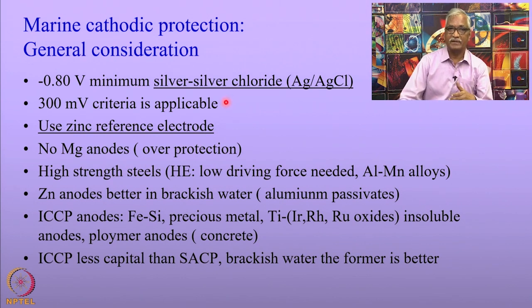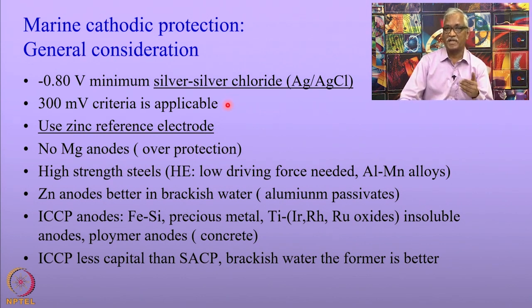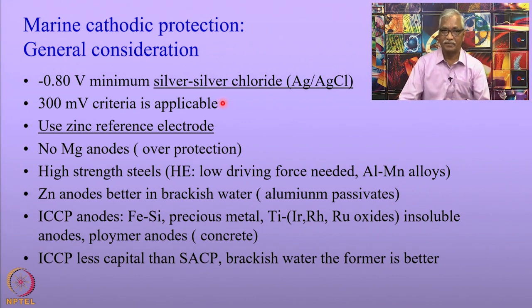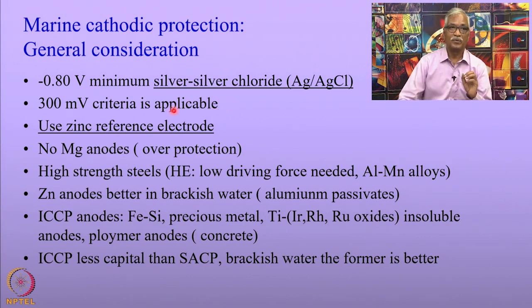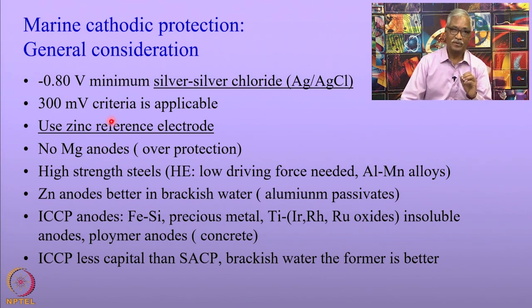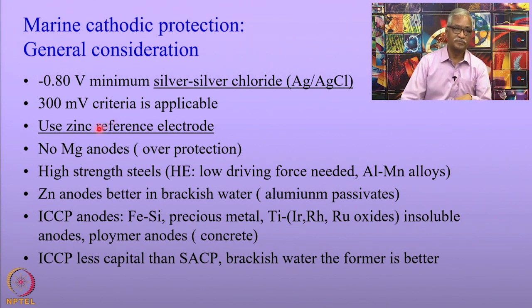Because the marine environment is high in chlorides, the copper-copper sulfate electrode is seldom used; instead, the silver-silver chloride electrode is used. The criterion for cathodic protection is minus 0.8 volts.